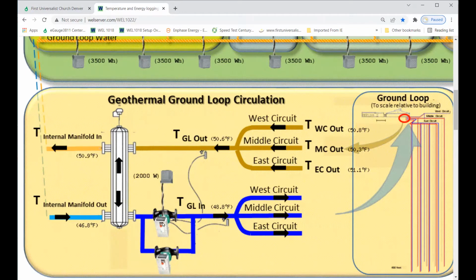Actually, there are 2 pumps. It's a redundant system. Only one is operating at any one time. And there's a control unit that switches from one pump on one day to another pump the next day. And it just alternates so that the 2 pumps are getting equal runtime. But this avoids a single point failure, so that if one pump did fail, our system would go down if we didn't have the backup.